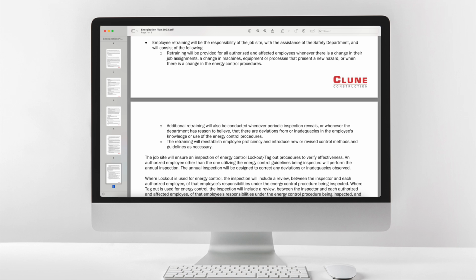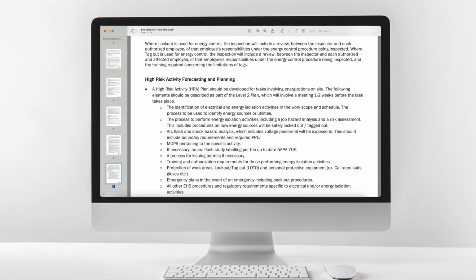The job site will ensure an inspection of energy control lockout, tagout procedures to verify effectiveness. An authorized employee other than the one utilizing the energy control guidelines being inspected will perform the annual inspection. The annual inspection will be designed to correct any deviations or inadequacies observed. Where lockout is used for energy control, the inspection will include a review, between the inspector and each authorized employee, of that employee's responsibilities under the energy control procedure being inspected. Where tagout is used for energy control, the inspection will include a review, between the inspector and each authorized and affected employee, of that employee's responsibilities under the energy control procedure being inspected, and the training required concerning the limitations of tags.